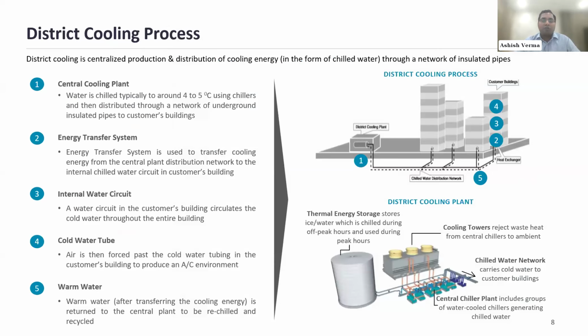Before going to that, I will just explain what a district cooling system is. District cooling is not a new technology. It has been existing for a long time in the Middle East, America, and other parts of the world. Mostly it was used as district heating, but hotter countries like the Middle East need cooling. That's why it's more popular there. So district cooling is nothing but a centralized production and distribution of cooling energy. Mostly the cooling energy is in the form of chilled water, and that is distributed to a network of buildings through a network of insulated pipes. And mostly these pipes are underground, connected to the district cooling plant.